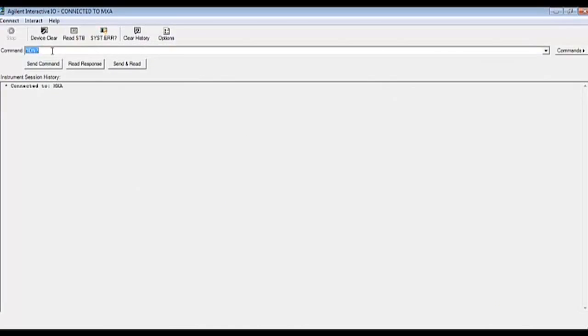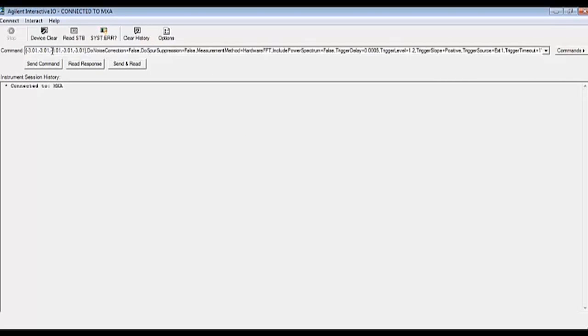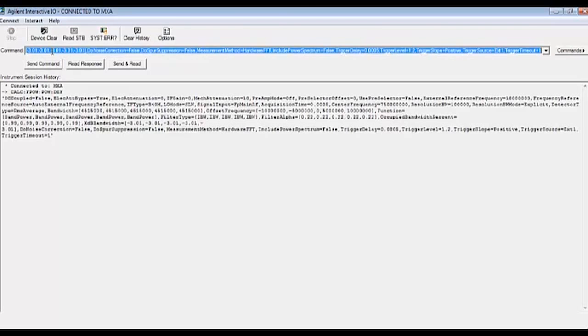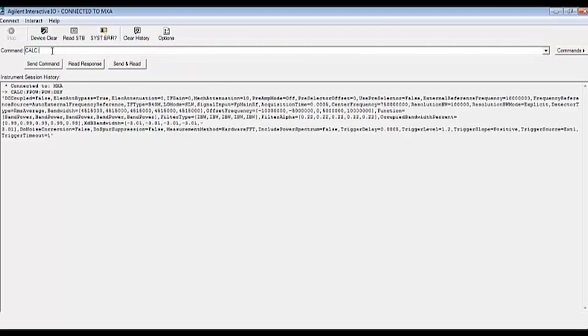By writing the FastPower SCPI def command we can now paste our definition in surrounded by single quotes. Now using the data query command we can perform the measurement and retrieve the channel powers in an ASCII format.